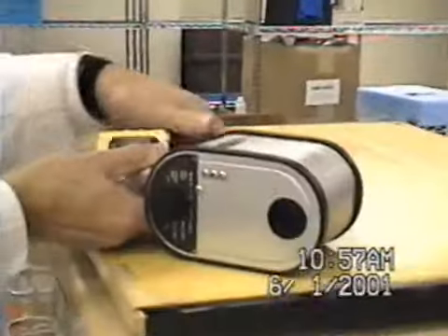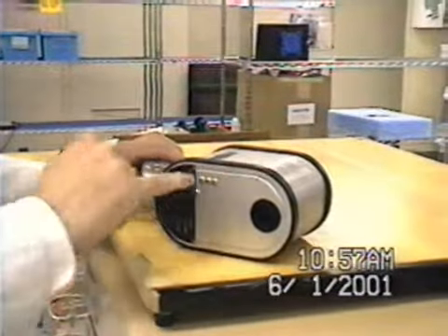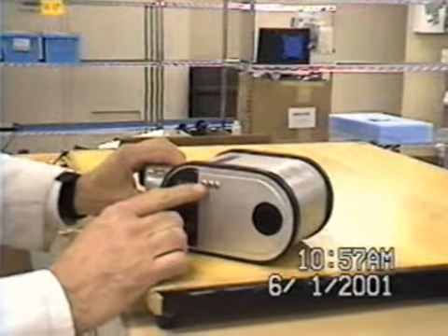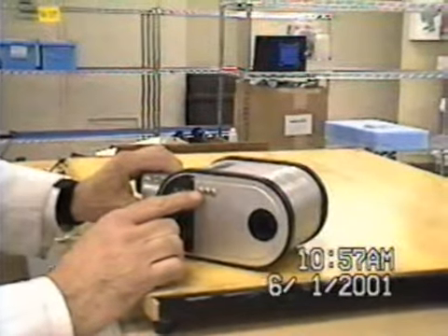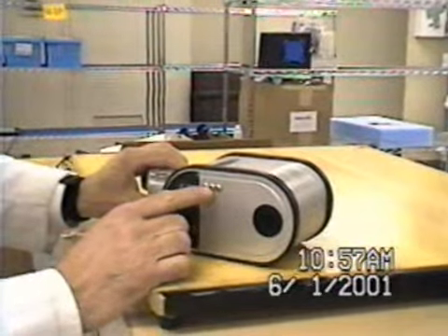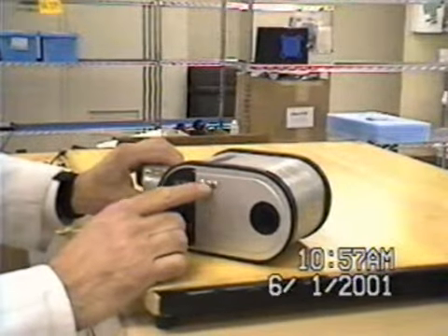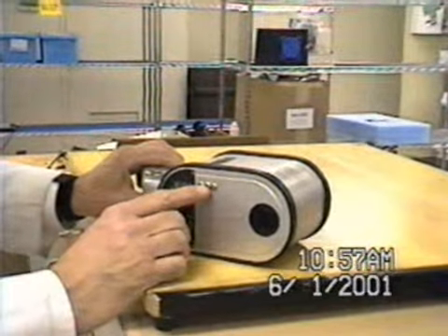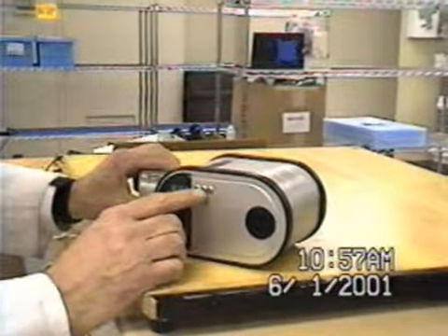Then you do the final adjustment, emissivity. This you don't touch. Theoretically, that is the radiance null, but you don't touch that. Emissivity null and emissivity span, those 2 you adjust. Looking at infinity for the null, and at the magnesium carbonate target, you set it to 10.